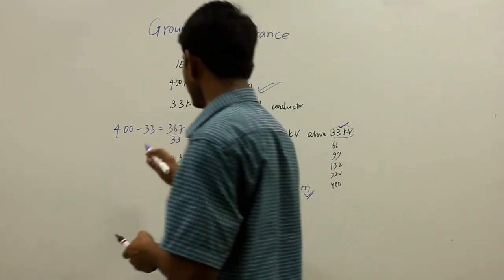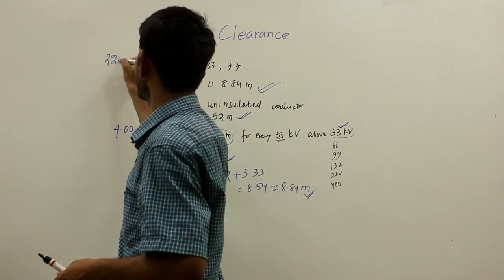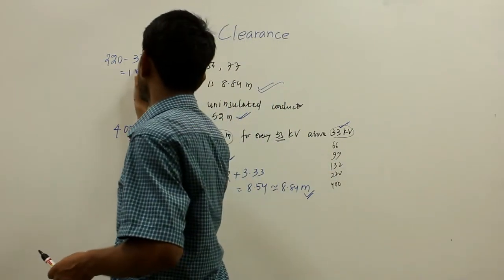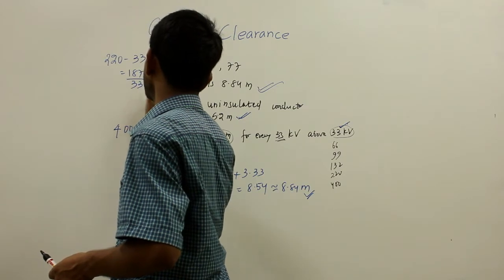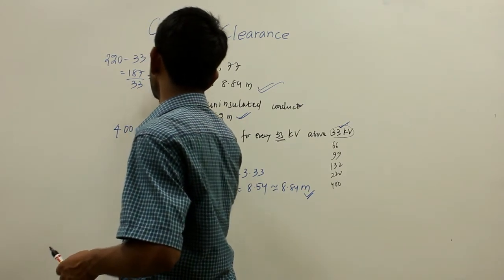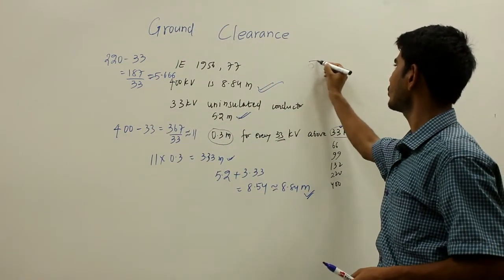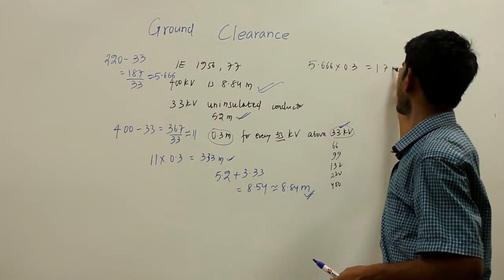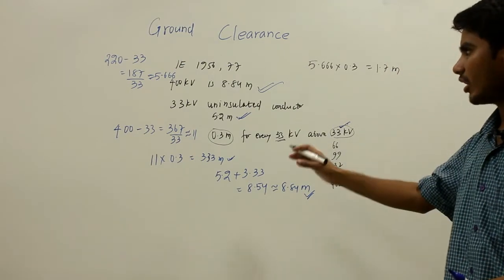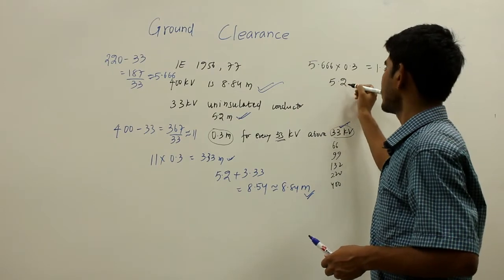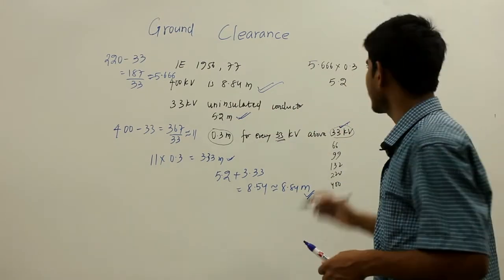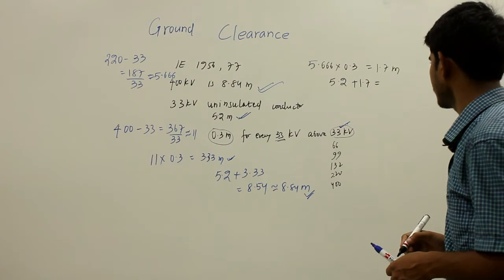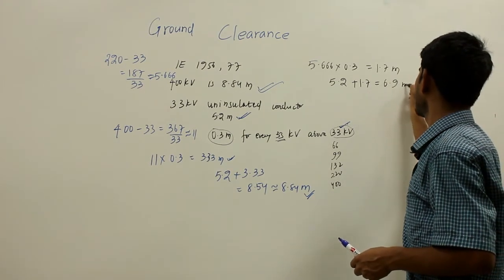Similarly, if we take a 220 kV transmission line: 220 minus 33 equals 187 kV. Dividing 187 by 33 gives approximately 5.66. Multiplying 5.66 by 0.3 gives 1.7 meters. So the minimum ground clearance of a 220 kV bottom conductor is 5.2 plus 1.7, which gives approximately 6.9 meters.